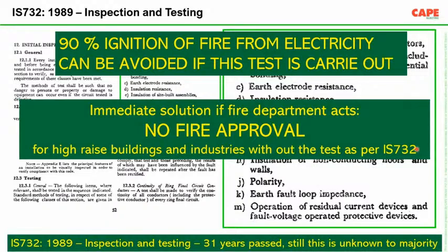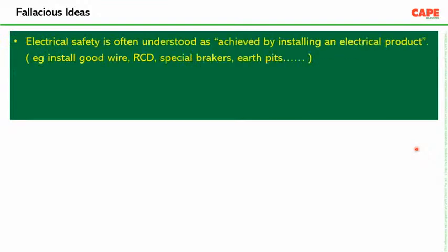Why? Because if the building is tested properly as per IS 732, all the problems which are going to come in future will be found out and we can rectify them very well. But instead of following this particular system, the complete installation concept, what we do is we always say that for electrical safety, let us put a good quality wire. Instead of FR wire, let us put FRLS wire. So by putting FRLS wire, I get safety.